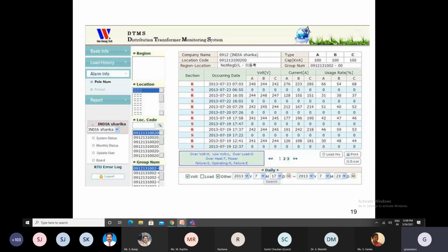It will be addressed, right? So, if there is a problem inside the oil, it will be communicated to the control center by means of a float there. So none of the transformers will be outaged, right? In our experience, most of the transformers are made outage because of the unbalancing of power. R phase only is largely loaded. Y phase and B phases are lightly loaded. Because right now we do not have a system in such a way that we know the loading point of the R phase, Y phase, and B phase.